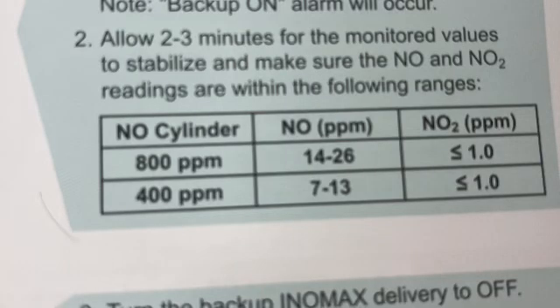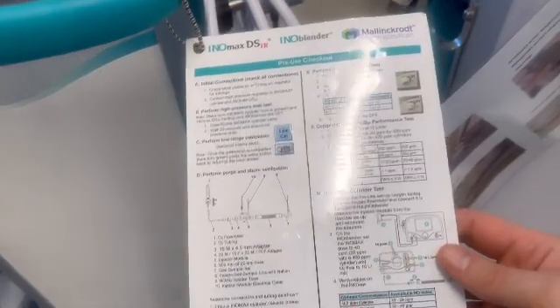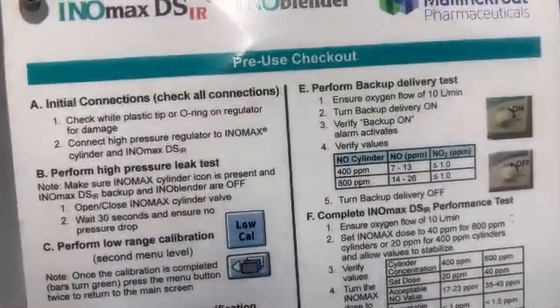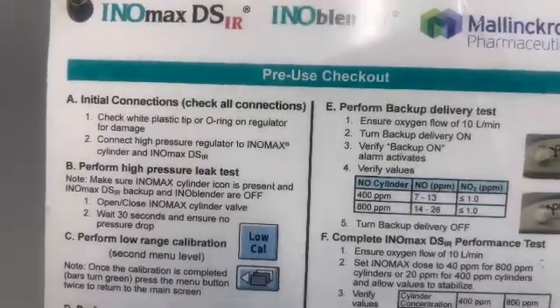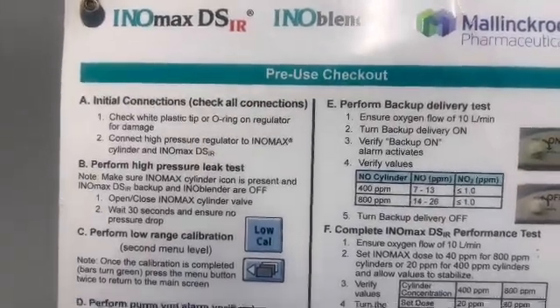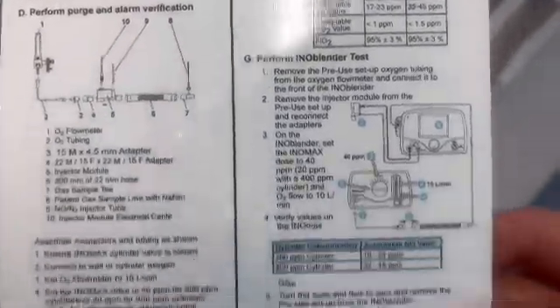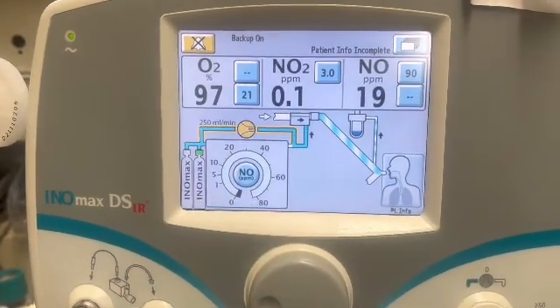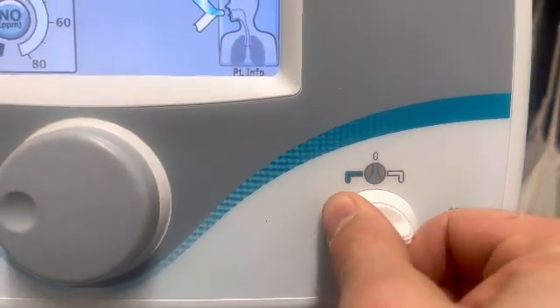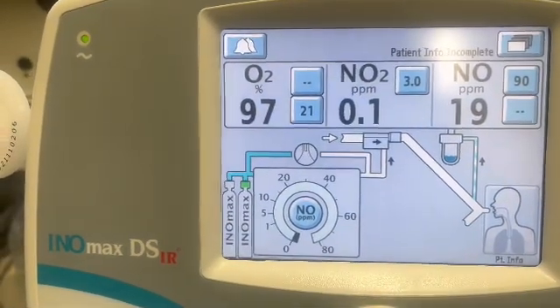Allow 2 to 3 minutes for the monitored values to stabilise and make sure the nitric oxide, or NO, reads between 14 to 26 and the NO2, or nitrogen dioxide, reads below 1. The information sheet attached to the two machines also details the rest of the pre-use tests that are required. When you're happy the dose is within range, turn the backup delivery to off, and you're ready to perform your next test.